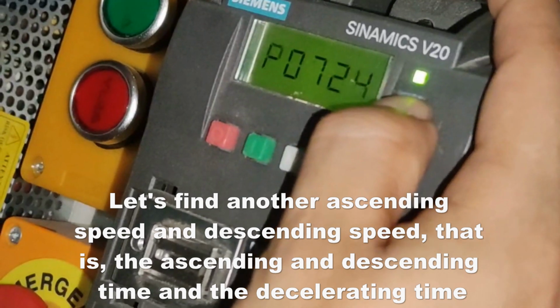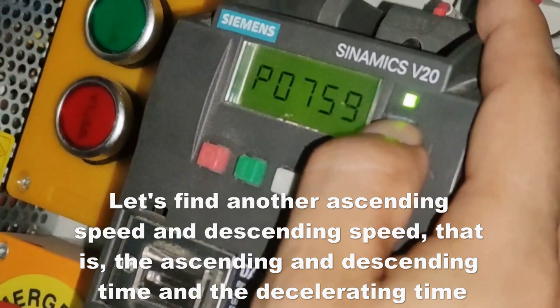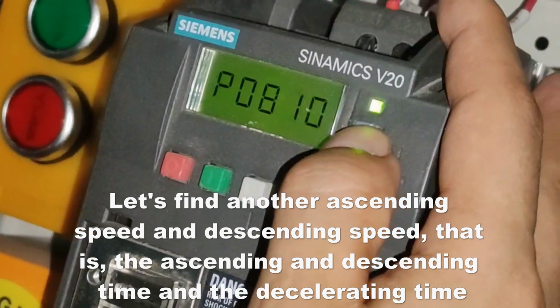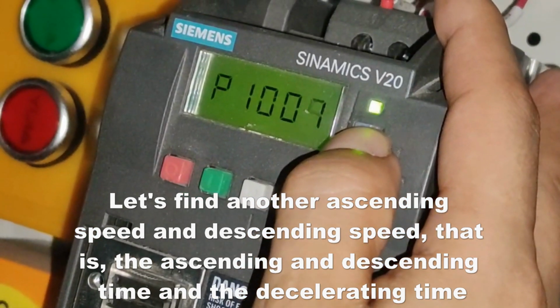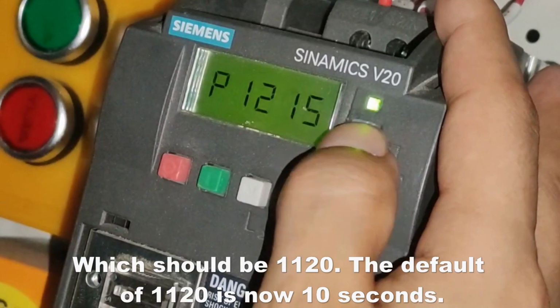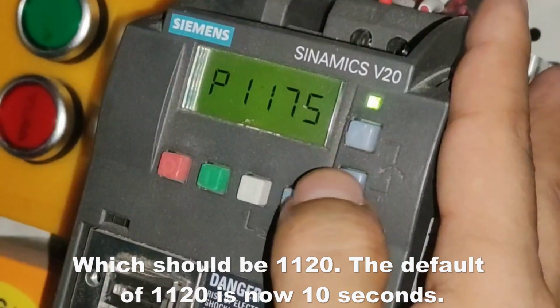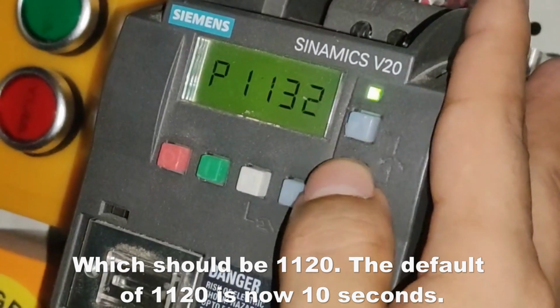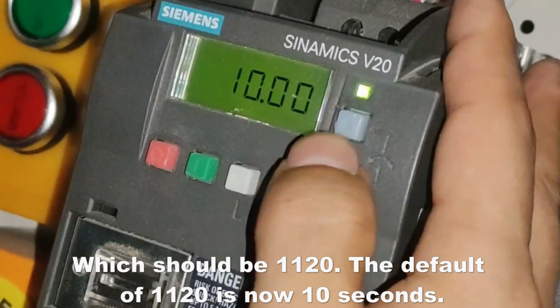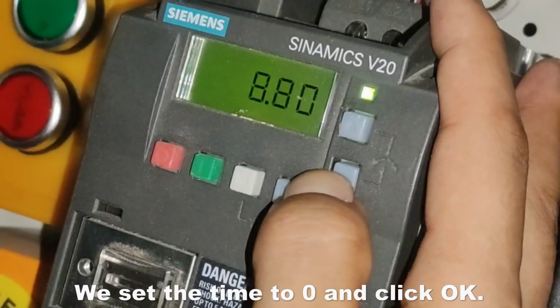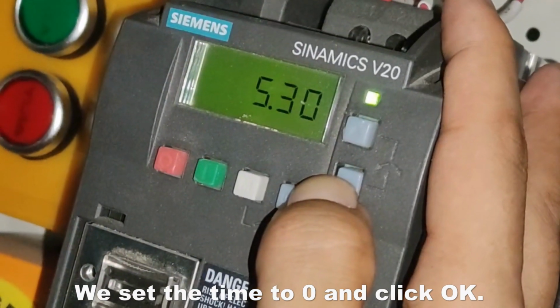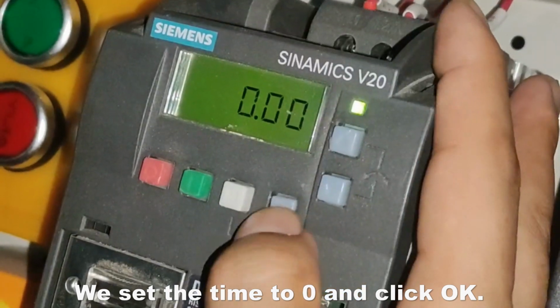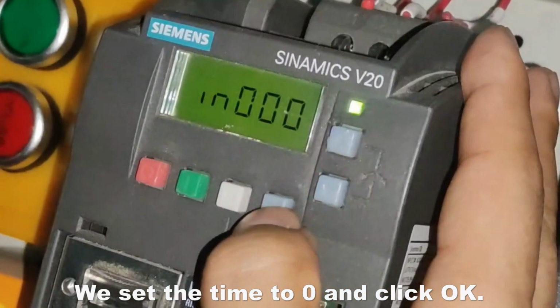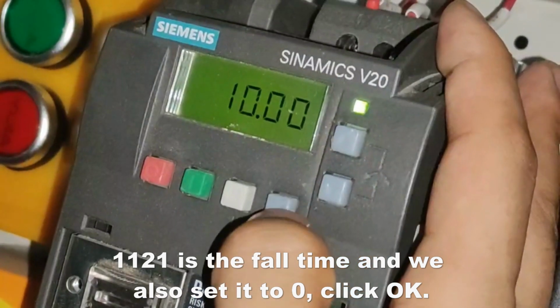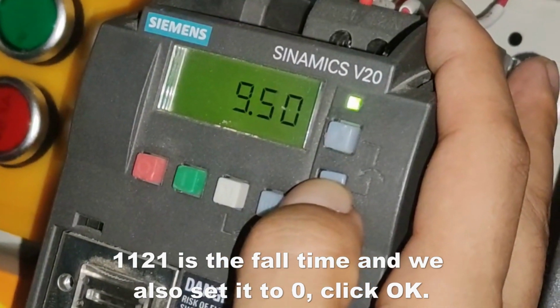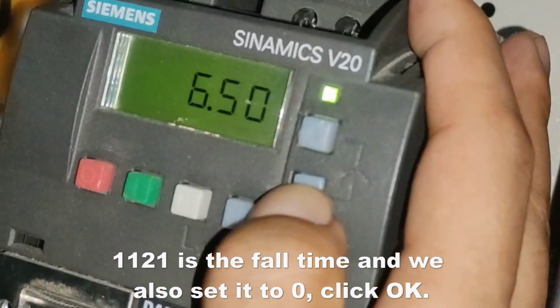Let's find another ascending speed and descending speed. That is the ascending time and the decelerating time, which should be P1120. The default of P1120 is now 10 seconds. We set the time to 0 and click OK. P1121 is the fall time, and we also set it to 0. Click OK.